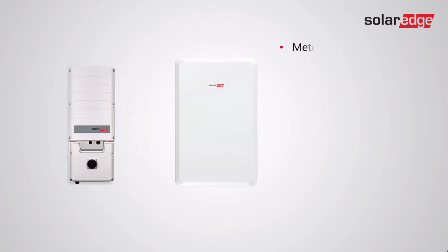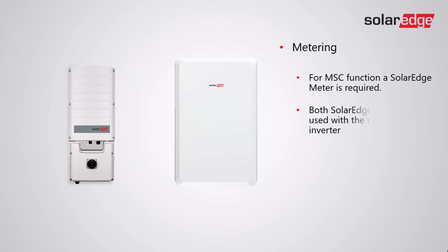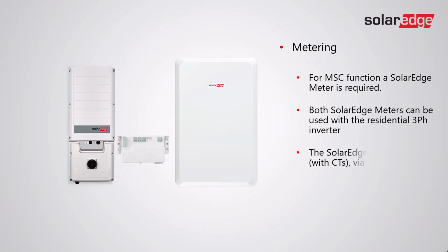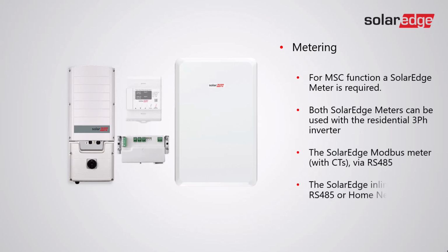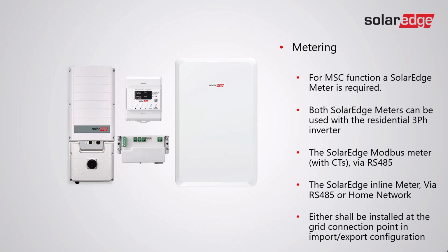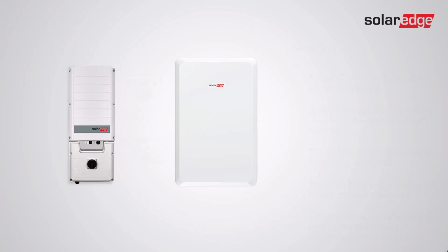With regard to metering, for MSC function, a SolarEdge meter is always required. Both of the SolarEdge meters can be used with a residential 3-phase inverter, that's the SolarEdge Modbus meter with CTs via RS485 connection, or the SolarEdge inline meter via RS485 or the SolarEdge home network. Either shall be installed at the grid connection point in import-export configuration.